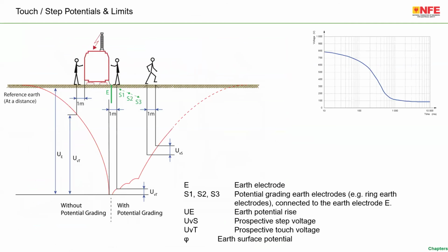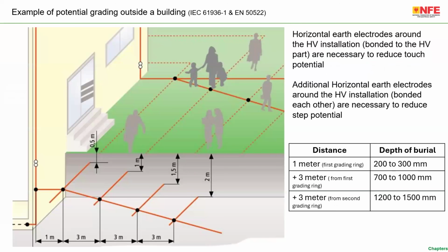Yeah, in this figure, you have seen the S1, S2, S3. This S1, S2, S3 is the potential grading. S1, S2, S3, potential grading earth electrode, a ring earth electrode connected to the earth electrode E. That means they are connected to the earth electrode and to the body of this particular transformer.